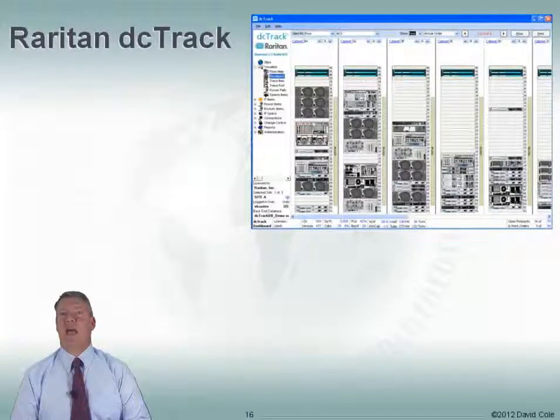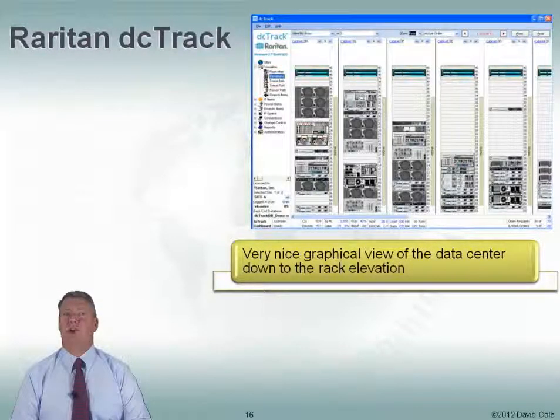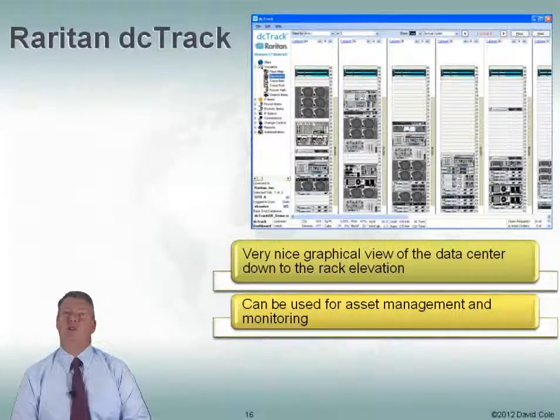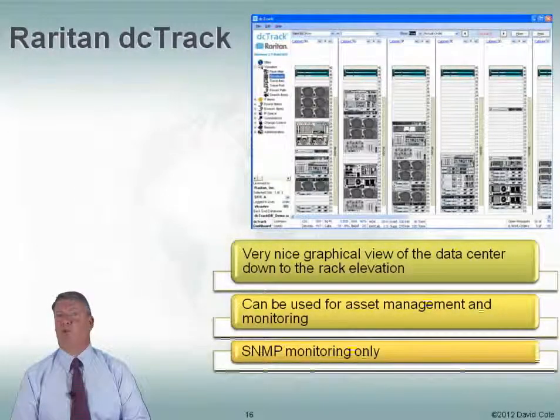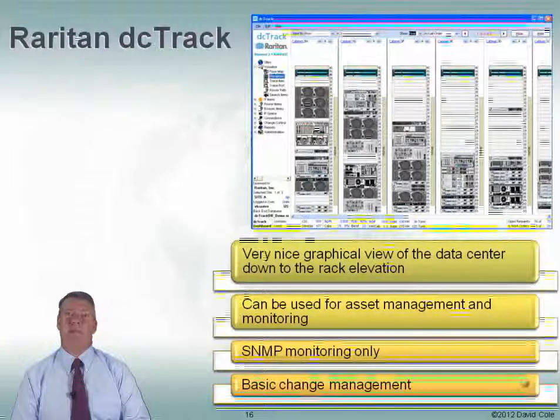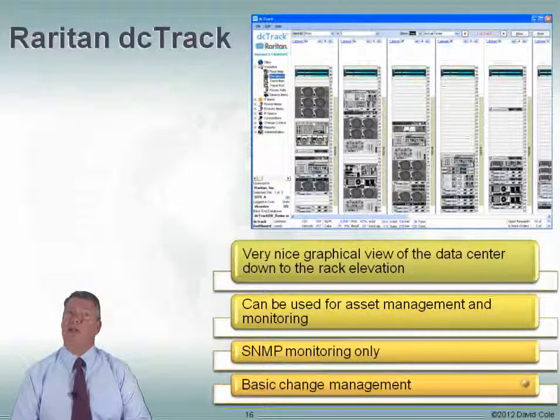Raritan DC Track is again a crossover tool — it has both an asset management tool and monitoring capabilities. They've got a nice graphical view of the data center down to the rack elevation, so you can see everything in your rack. You can use it for both asset management and monitoring. It only monitors SNMP for the protocol. They do some basic change management — as you manually change things, it will write that into a change management log. It's not automatic, but it does give you some change management capabilities.